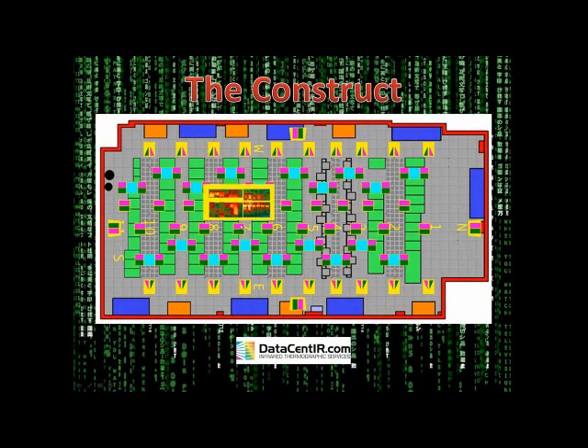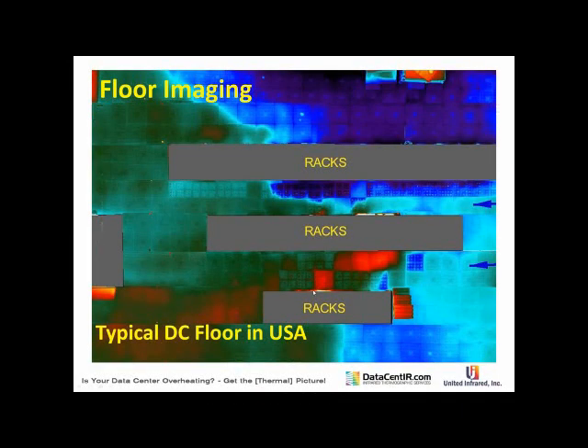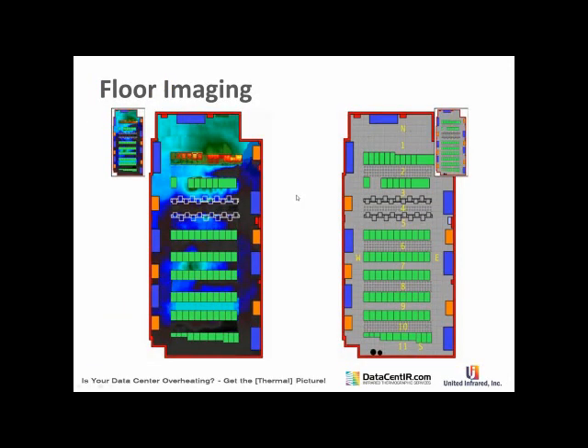So let me just go back to this PowerPoint for a minute. Again, the big problem in these data centers is the hot aisle, cold aisle, because it's really supplying the cold air that's going into these racks, and the temperature of that air going to the inlet, there's your weakest link. As I showed on the website, the 2D imaging is basically doing this kind of thing right here. It's really very intuitive. You just roll your mouse in, and it zooms in to where you could read the newspaper. And this particular data center, which John showed before, has an obvious problem.